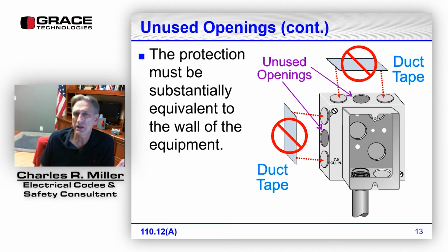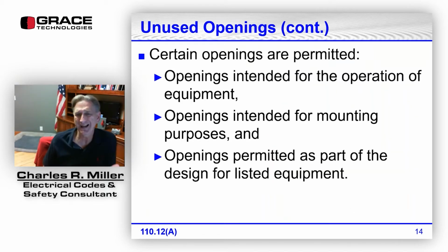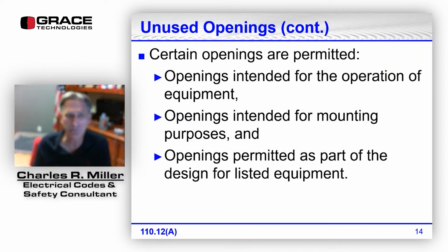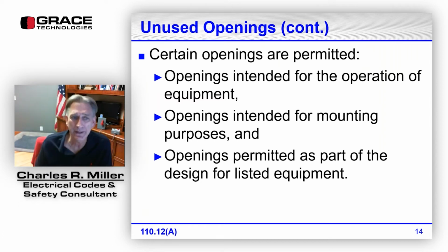All right, I mentioned not all unused openings have to be closed. Well, this was understood for years and years in the code book. And then I guess some people figured out, well, wait a minute, we can't close every opening in a junction box or panelboard. And so there was a code change put in a number of editions back, and it said certain openings are permitted. Well, what are they? Openings intended for the operation of the equipment, openings intended for mounting purposes, and openings permitted as part of the design of the equipment.